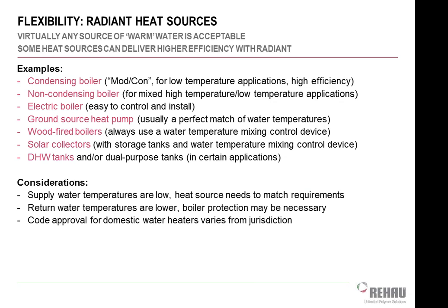You could also certainly use an electric boiler, although here in the Midwest, natural gas is pretty cheap, so an electric boiler doesn't make a huge amount of sense, although it may be better than propane for some customers depending on your propane cost. You could couple these radiant floor systems to ground source heat pumps, which is a fantastic energy saver, obviously. It's hard to put a regular heating system, hydronic heating system on a ground source heat pump because you can't get the 160 or 180 degree water.